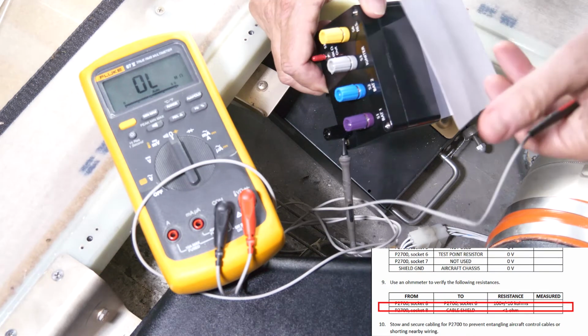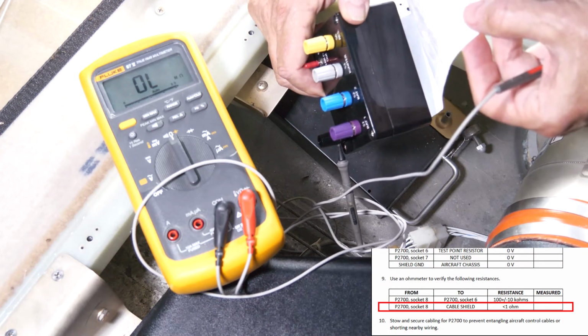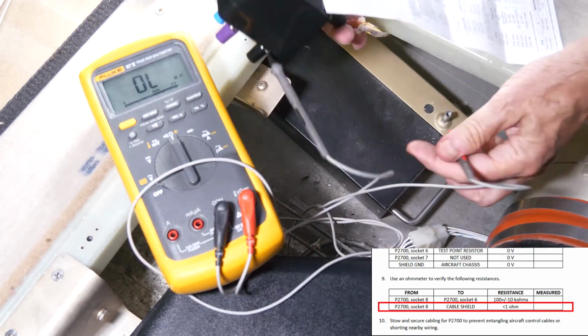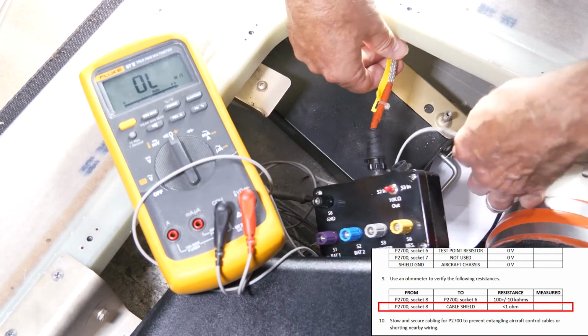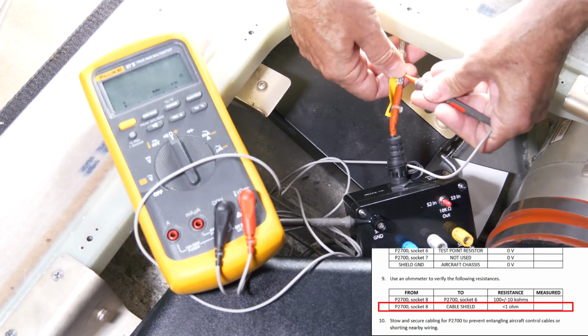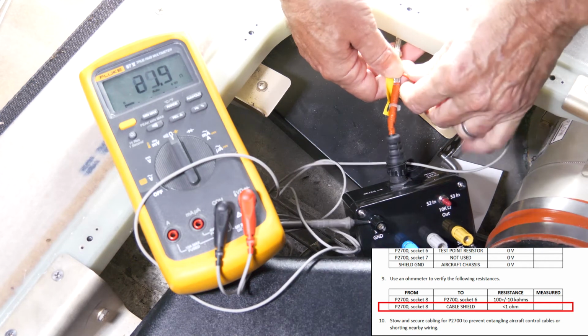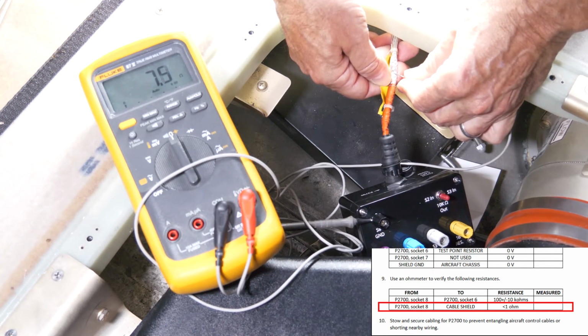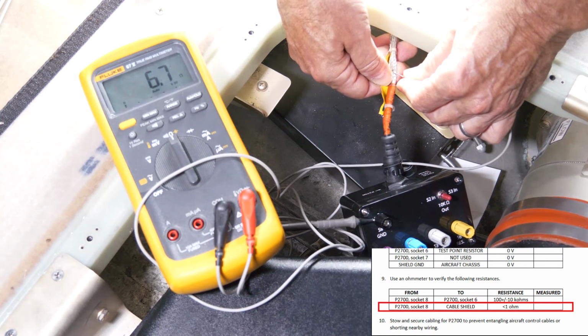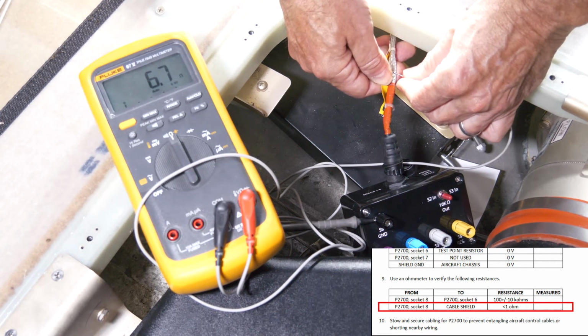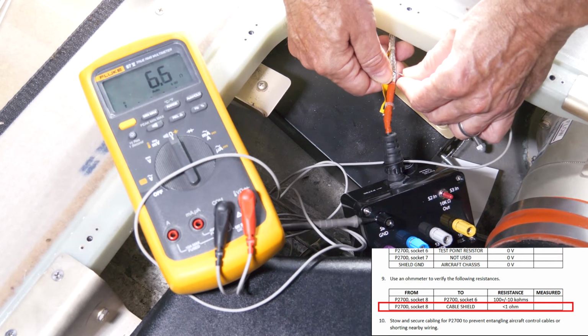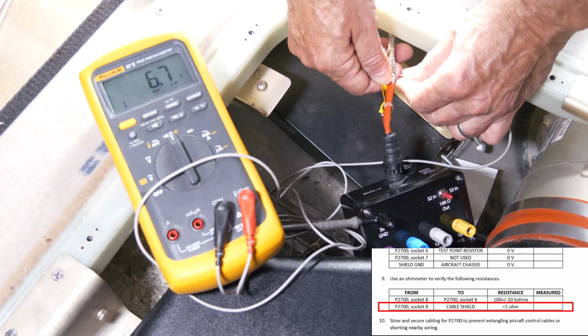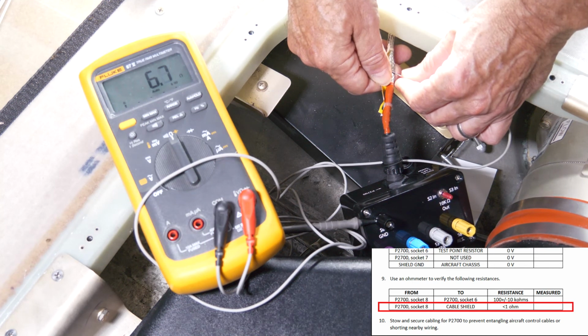And then the last one is the cable shield, which is supposed to be less than 1 ohm. When I was testing that earlier I was getting an open circuit, but now, okay, so now it's a low resistance, 6.7 ohms, and I'm going to call that less than 1 ohm because these meters don't really read well at such low resistances. I'd need a special meter or adapter to accurately go below 20 ohms or so.